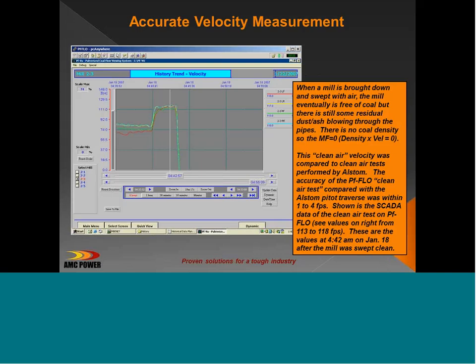Again, this is an example of velocity. I'm going to show you several screens throughout the course of this presentation. Some will be the mass flow of coal, and some will be the speed or velocity of the coal. This is a typical velocity screen as presented by our equipment. And if we were to look at our mass flow screen at this point in time, this is the fuel velocity, the mass flow would drop to 0 because this plant shut the feeder off.